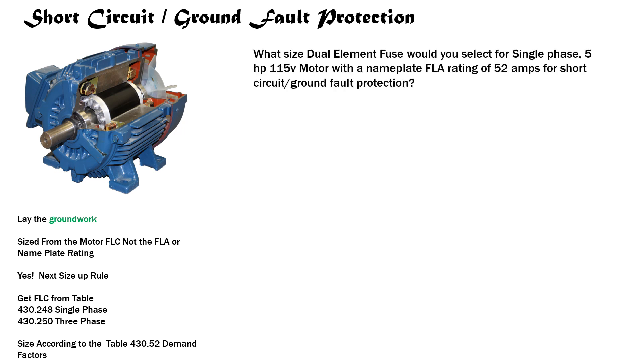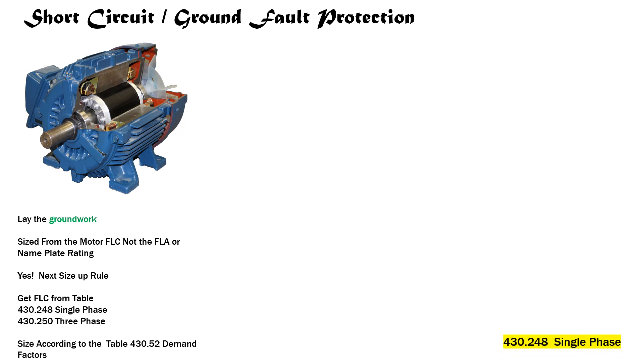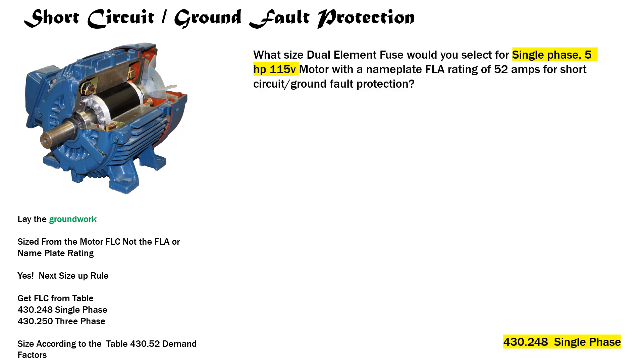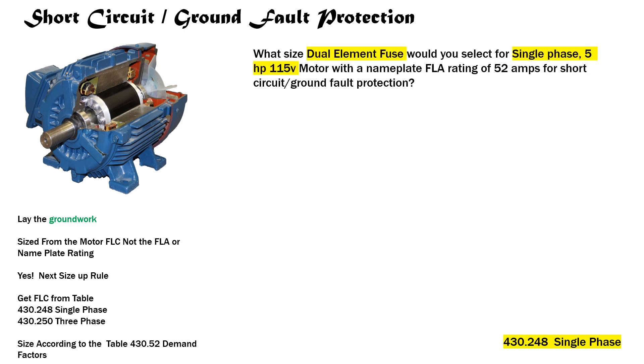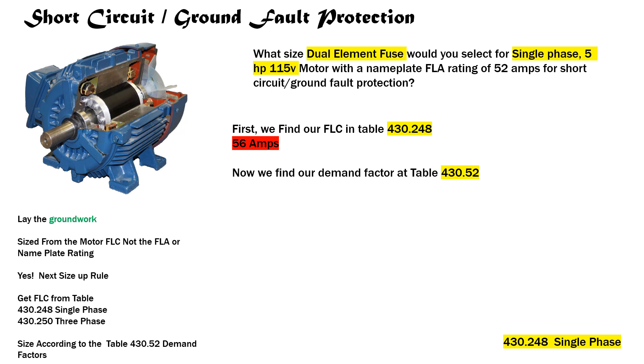What size dual element fuse would you select for a single-phase, five horsepower, 115 volt motor with a nameplate FLA rating of 52 amps for short circuit ground fault protection? First we identify it's single-phase, five horsepower, 115 volts, and a dual element fuse. We find our FLC in table 430.248 — on the left side for horsepower, across the top for voltage — and our FLC is 56 amps.